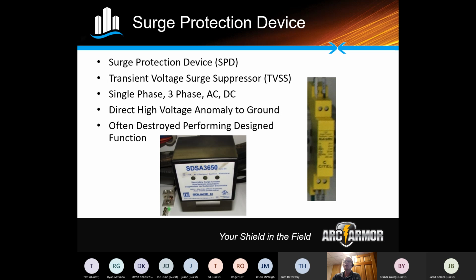So if something were to get on that, it can short that. It won't take out the input card, or the device out in the field. But more than likely, if you do get hit, you have to replace that surge protection device out there.